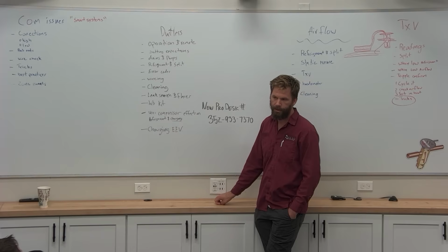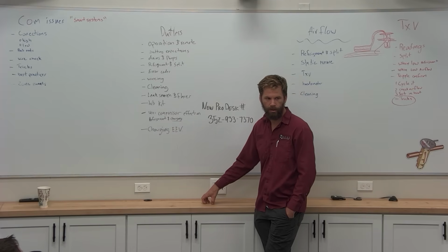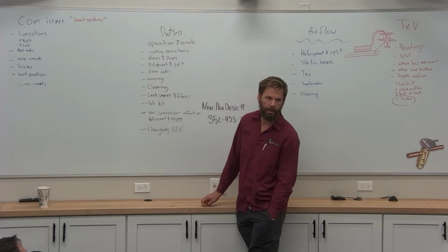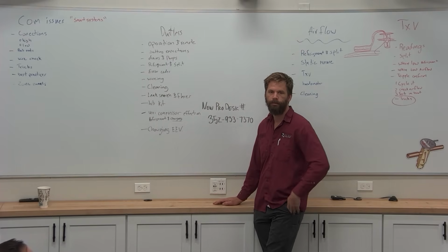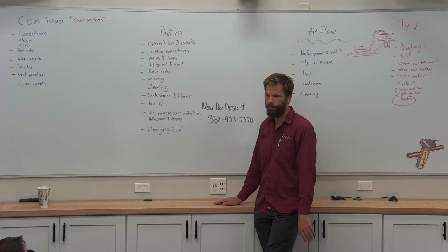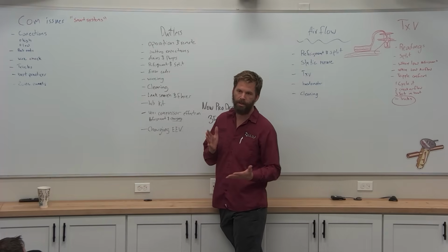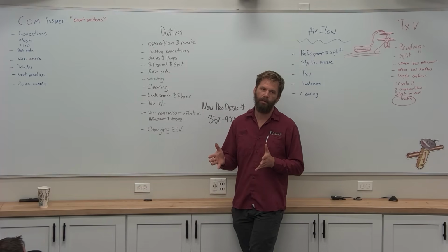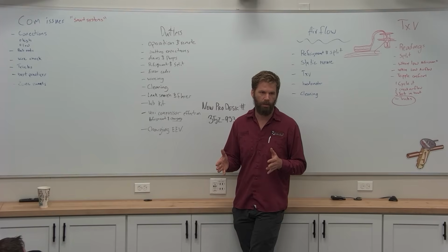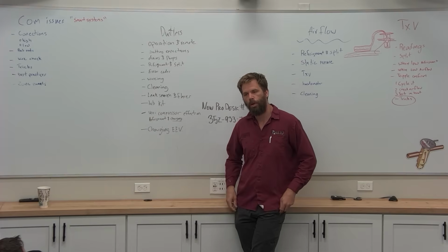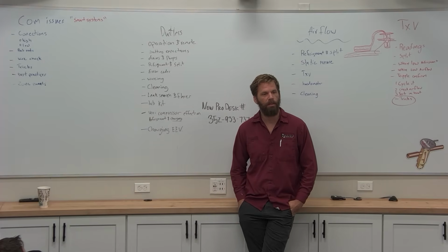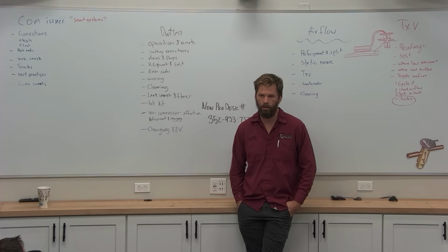We are told that we can't, and it is common practice in ductless units not to charge them. And why is that? It's easy to overcharge. Very easy to overcharge. Critical charge, which is the same thing. They need to be pretty exact. If you go over the amount of refrigerant that it should have, it causes a lot of problems with the compressor trying to run full speed, going out on high head. So if you're slightly under, the system will usually run decently well, slightly low on charge. So if you're gonna mess this up, I'd rather you be under rather than over.